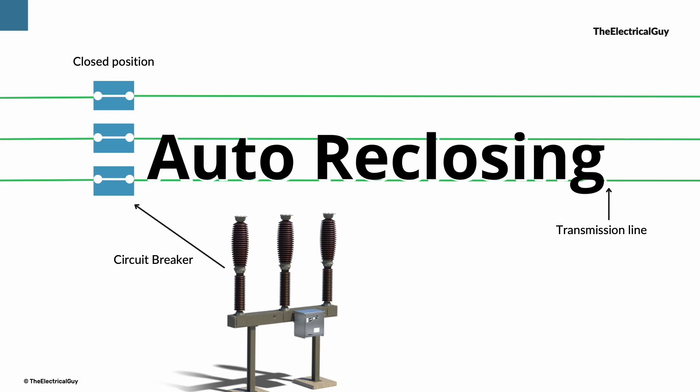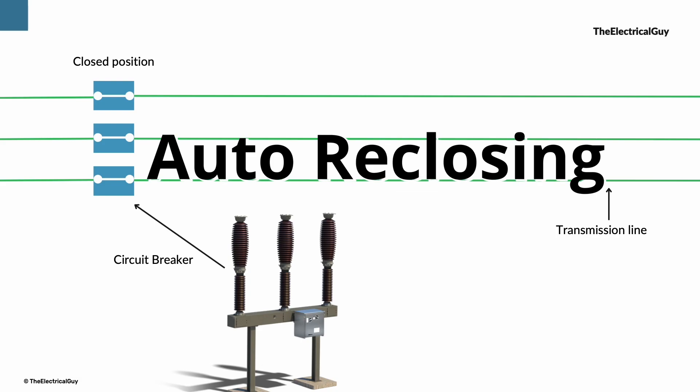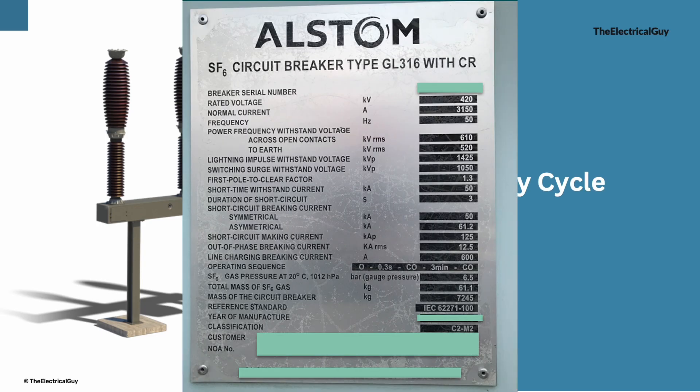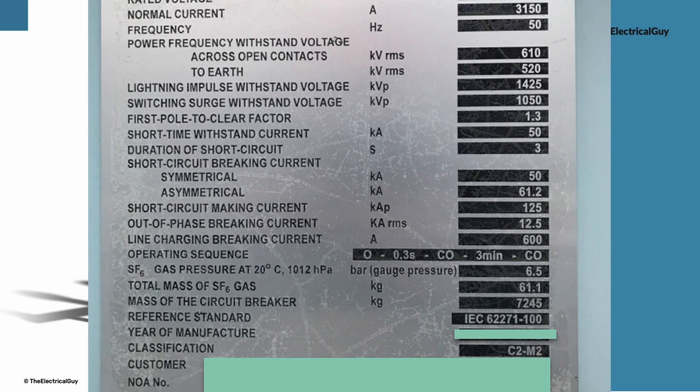So that is nothing but the auto reclosing. Now let us talk about duty cycle of a circuit breaker. If you would have seen a nameplate of a medium or high and extra high voltage circuit breaker, you would have seen something called as duty cycle or rated operating duty cycle, or few people also call it as auto reclosing cycle.